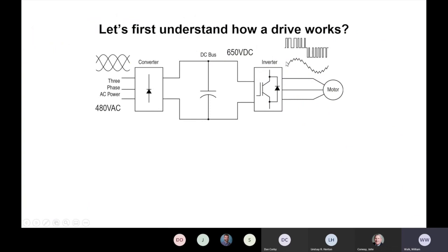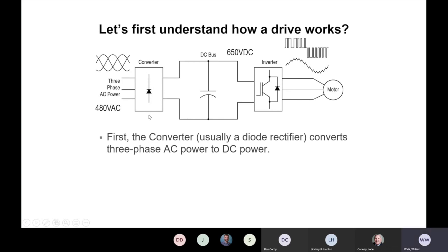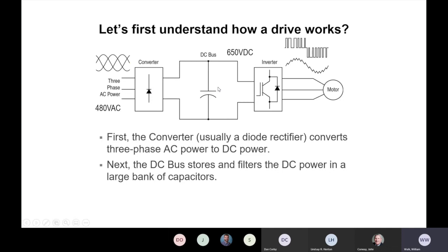So let's first understand how a drive actually works. John, can you see my cursor? Or Lindsay? Yes, we can. Okay. We have 3 sections inside the VFD: the converter section, the DC bus, and the inverter section. The converter section takes, for this example, 3-phase AC power at 480 volts and converts it to DC power. Next, the DC bus stores and filters that DC power in the large bank capacitors, and it chops that over into the inverter section of the VFD.